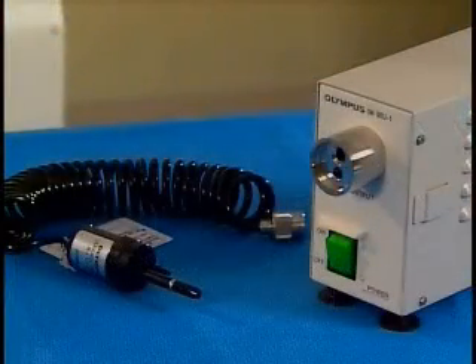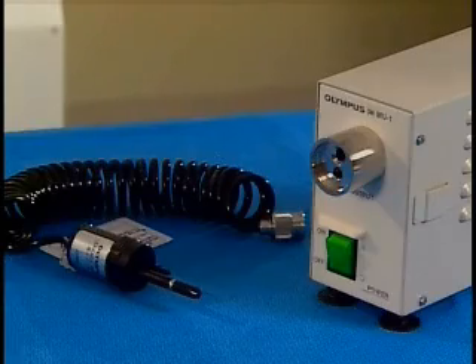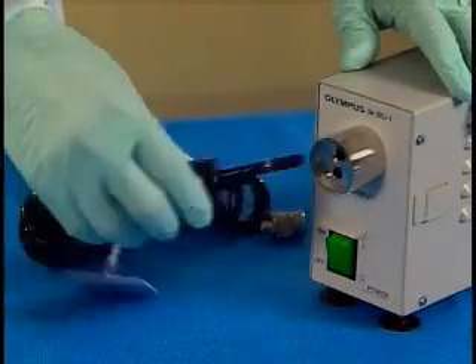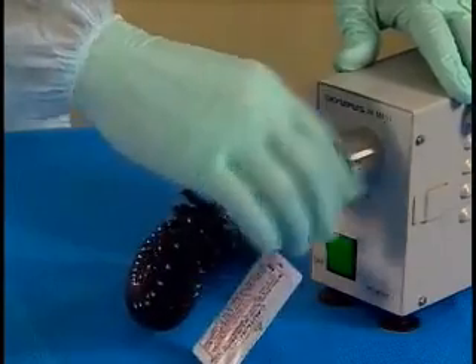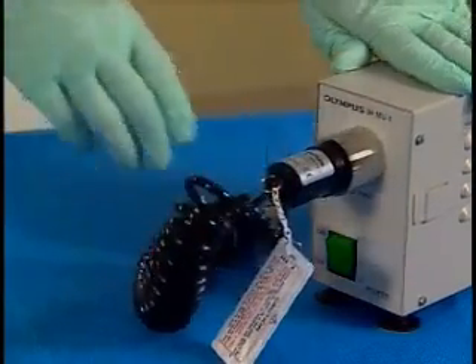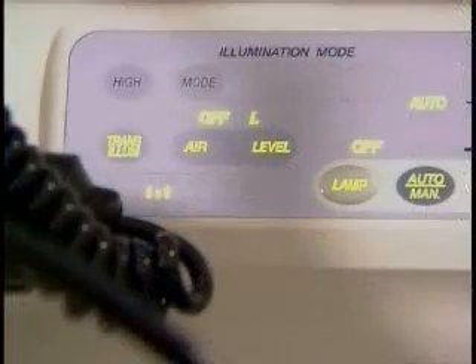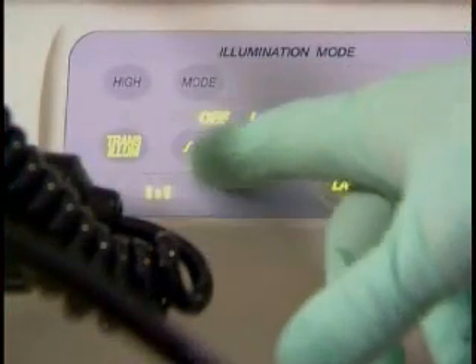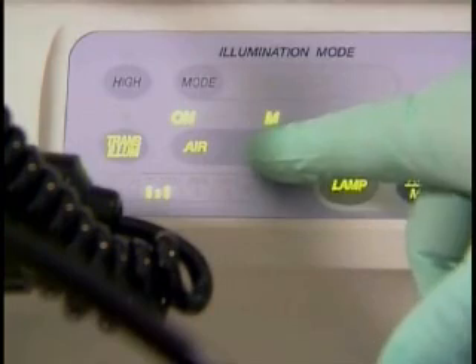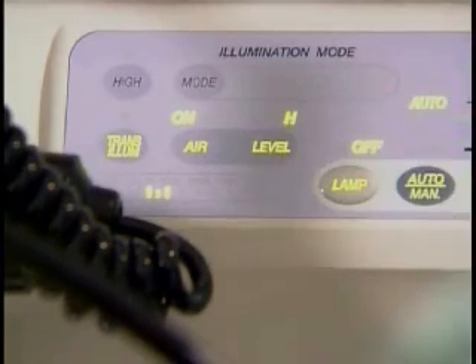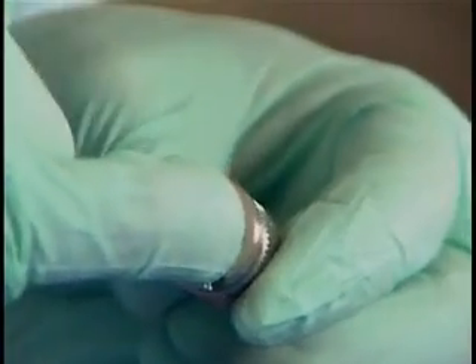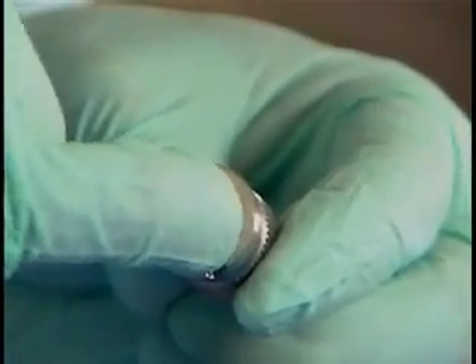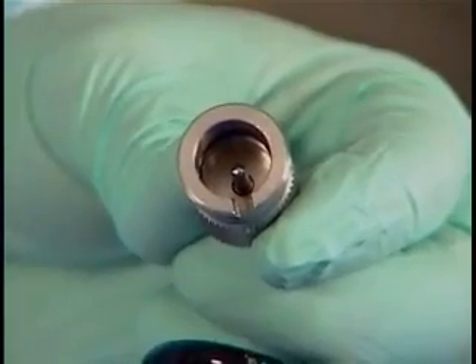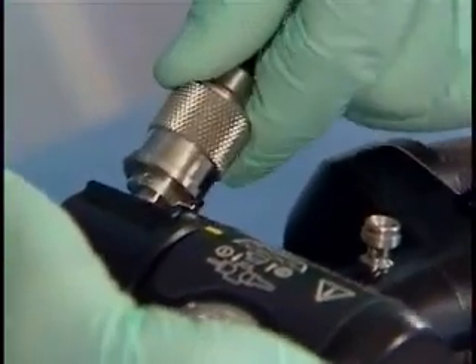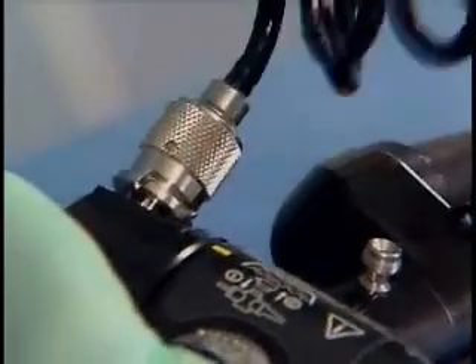Now, we are ready to proceed with leakage testing. Attach the leakage tester to the MU1 maintenance unit or to an Olympus light source. Turn on the air supply. If you are using a light source, be sure to set the airflow rate to its maximum setting. Depress the pin inside the connector and confirm that air comes out of the cap. Now, attach the leakage tester to the endoscope.